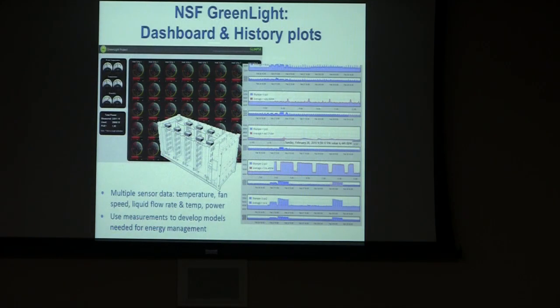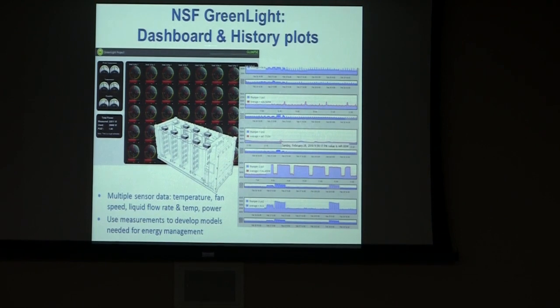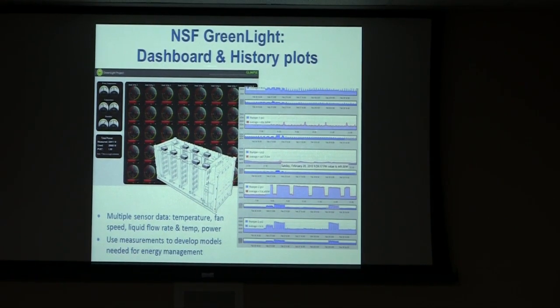To get started, here's a sample of what the data from our Greenlight infrastructure looks like. On the left is the container level data, showing temperature, humidity, current power usage efficiency, and current power levels within the data center box. In the middle are the racks—8 racks, so 8 columns. In each column you can see fan speeds and temperature distribution per rack. If you click on any individual area, you can see the power consumption, and if you zoom in further, you can see power plots for every individual server.